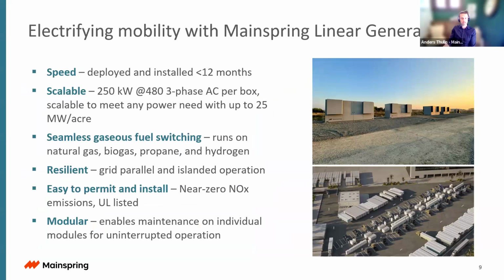Specifically, a linear generator from Mainspring—several deployments throughout the country, heavily in California—because it's a tool used both for reducing cost of projects and tying together with other grid assets or DERs. The solution is a 250 kW, 20-foot ISO container, 480 3-phase AC power out per unit, scalable up to 25 megawatts per acre to meet specific load requirements.